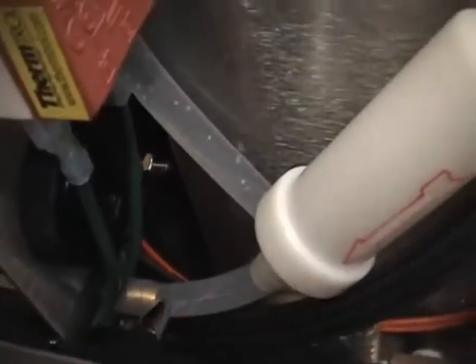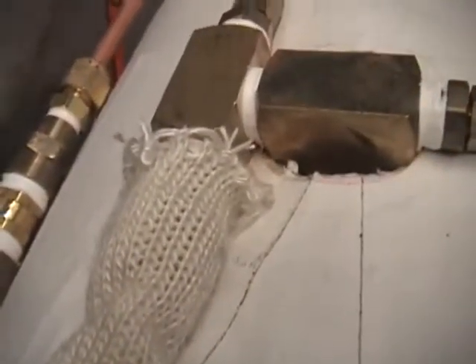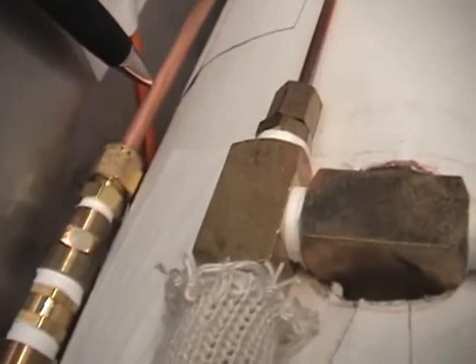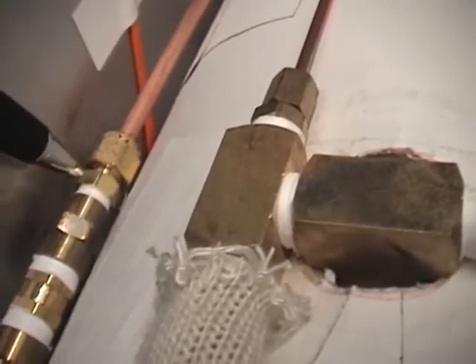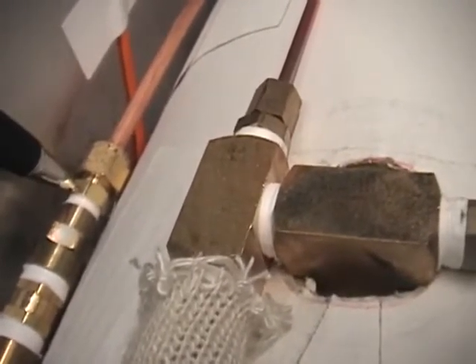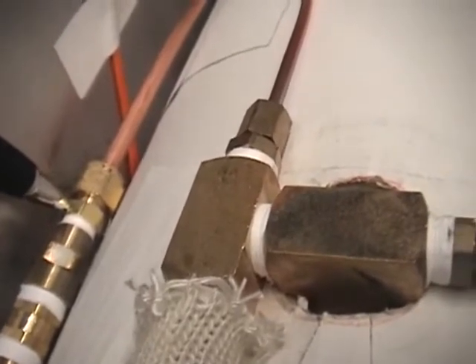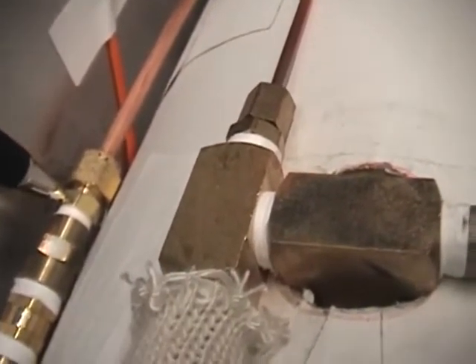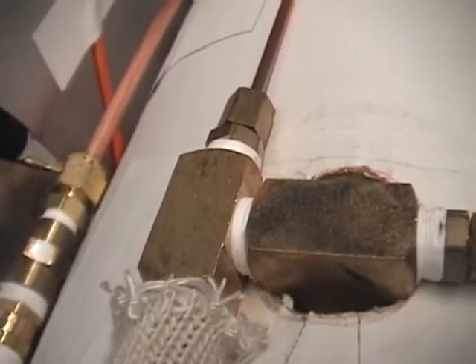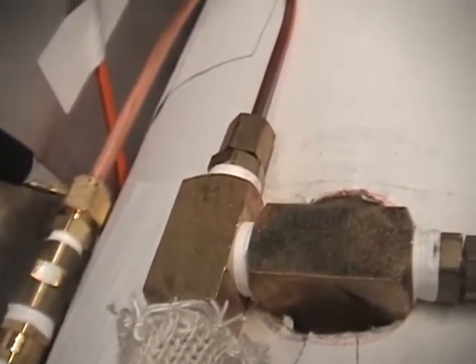Pull back this clear hose that is inserted into a barb. Next, you'll need to remove this black hose that is connected onto this 1/4 inch copper line. By doing that, you can use a 1/2 inch wrench on this side to hold the compression fitting, and then loosen the cap with a 9/16 wrench.